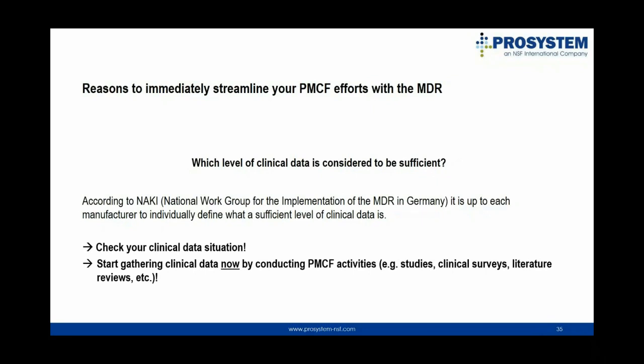Some devices that have been on the market for years or even decades may see their clinical investigations dismissed as inadequate because they are not compliant with the current version of the Helsinki Declaration or the ISO 14155, or do not meet higher demands for medical scientific relevance. This is why PMCF studies could help bridge the gap, and this is why you should have started gathering clinical data yesterday.